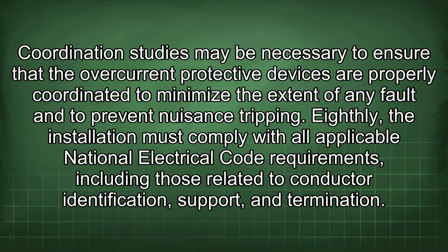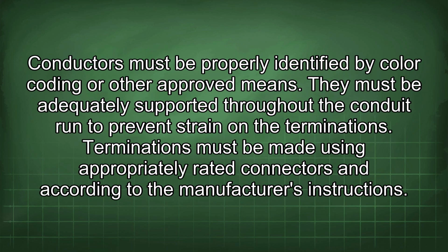Eighthly, the installation must comply with all applicable National Electrical Code requirements, including those related to conductor identification, support, and termination. Conductors must be properly identified by color coding or other approved means. They must be adequately supported throughout the conduit run to prevent strain on the terminations. Terminations must be made using appropriately rated connectors and according to the manufacturer's instructions.